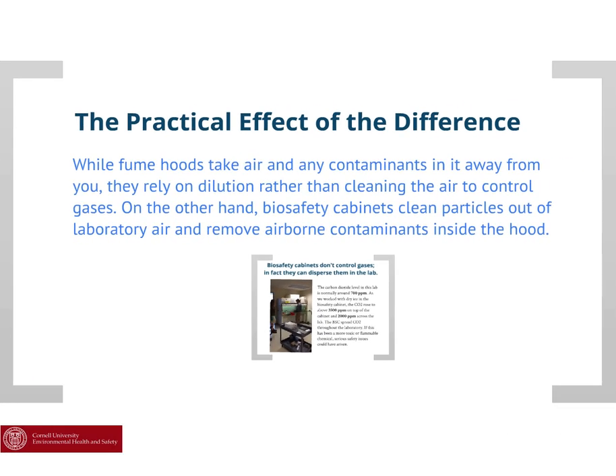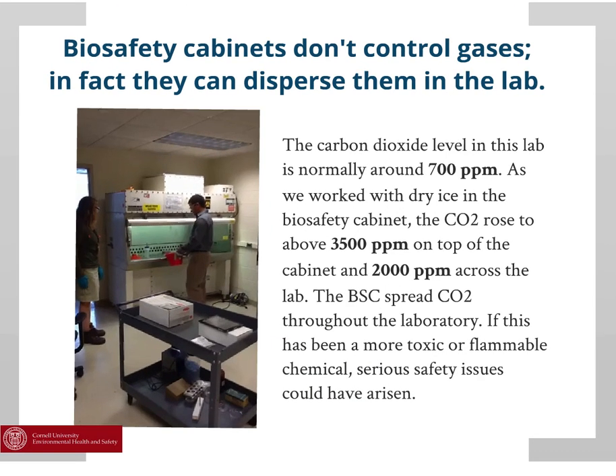The practical difference between biosafety cabinets and fume hoods is significant. While fume hoods take air and any contaminants in it away from you, they rely on dilution rather than cleaning the air to control gases. On the other hand, biosafety cabinets clean particles out of laboratory air and remove airborne contaminants inside the hood. Biosafety cabinets don't control gases — in fact, they can disperse them throughout the laboratory.